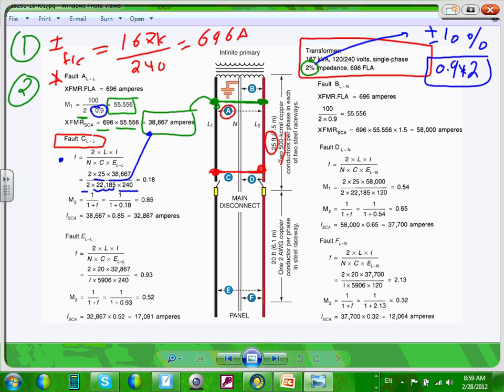So if you guys go to this page, this will give you the C factor for conductors. They call it the C factor. That takes the impedance of the conductors into consideration. The first thing you need to decide in this table, guys, is: is it a copper conductor? Yes. The bottom of the table is actually for aluminum. One for copper, one for aluminum. The last one is for busways. Cool? All right, let's look at the upper one because it's copper.